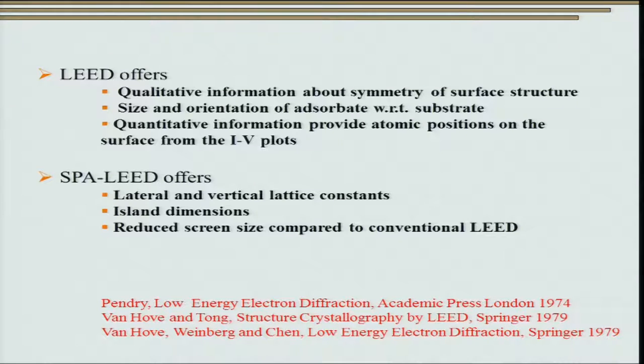We are going to cover the IV plots aspect in the next few slides, though it is a very involved topic and we will just touch upon what we can do with IV plots rather than going into detailed surface structure analysis. SPA-LEED gives information about the lateral and vertical lattice constants of islands on the substrate and provides complete island dimensions. However, SPA-LEED has a smaller screen size compared to conventional LEED. Depending on our need, we can choose either LEED or the SPA-LEED option. Since we are using electrons, we can also use the same setup as an electron microscope to image a region of interest before getting diffraction.